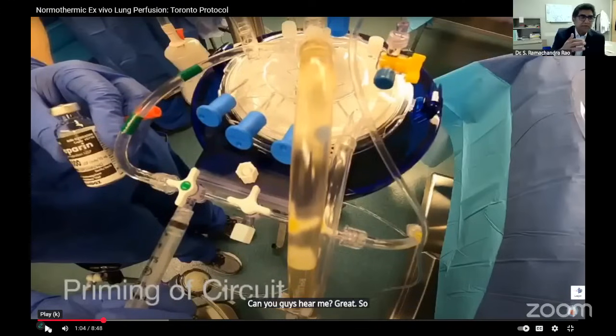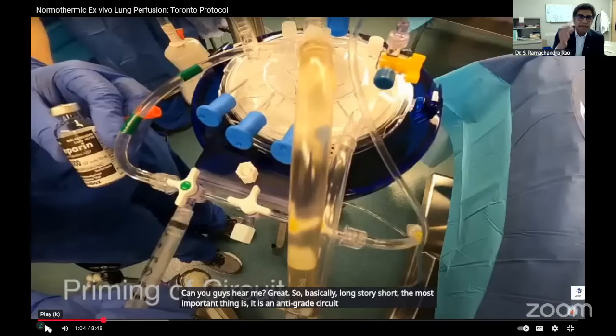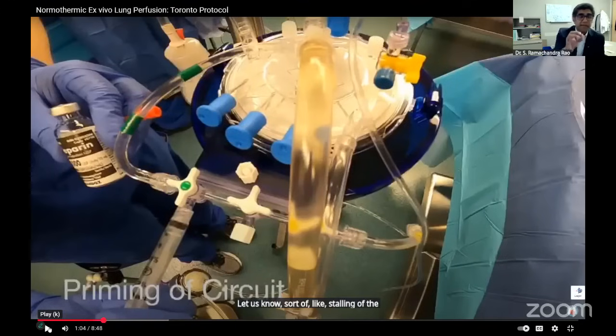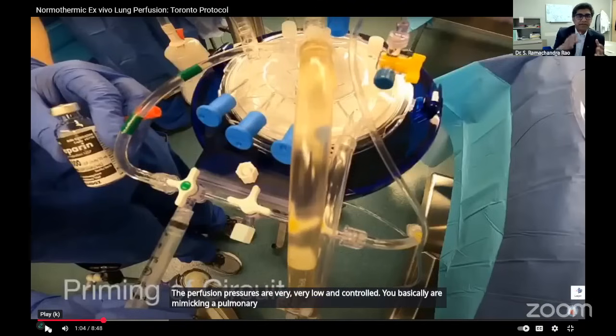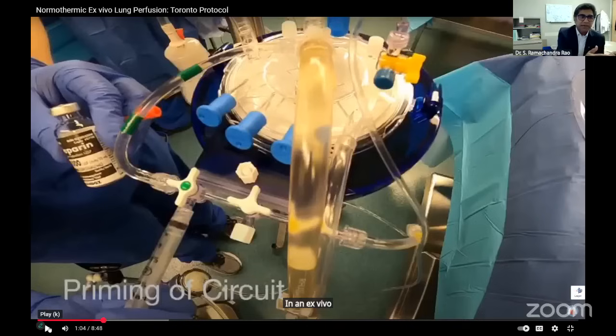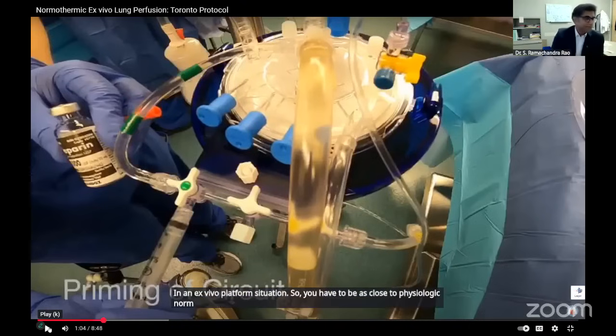So basically, long story short, the most important thing is it is an antegrade circuit. You need that one-way valve, extremely important, so that there is no stalling of the perfusate, because the perfusion pressures are very, very low and controlled. You are mimicking a pulmonary arterial circuit and a pulmonary venous drainage circuit in an ex vivo platform situation, so you have to be as close to physiologic norms as possible.